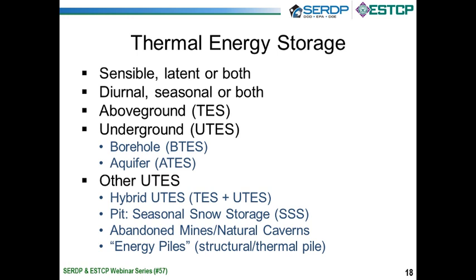Generally, if we're above ground, you just call it thermal energy storage, or sometimes TES. Underground, it's considered UTES, or underground thermal energy storage. And since this was a military project, we will be burying you in acronyms today. There are two different flavors of it. One is borehole thermal energy storage, so-called BTES. That's what we did at Albany at roughly a 400-ton scale. Or aquifer thermal energy storage, so-called ATES. The ATES system at Fort Benning involved brigade headquarters, roughly about 35 tons.